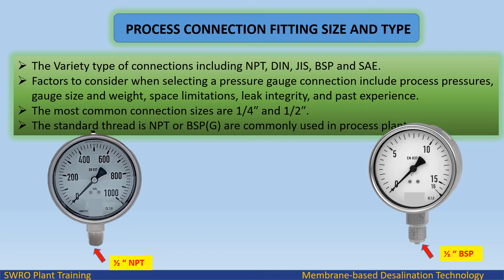Process connection fitting size and type: A variety of connection types are available, including NPT, DIN, JIS, BSP, and SAE. Factors to consider when selecting a connection include process pressures, gauge size and weight, space limitations, leak integrity, and past experience. The most common connection sizes are quarter inch and half inch. The standard thread types NPT or BSP (G) are commonly used in process plants.